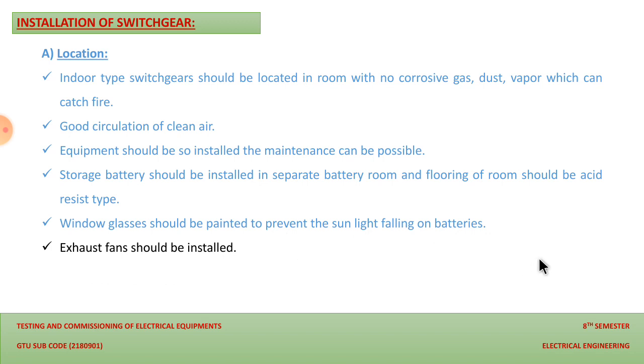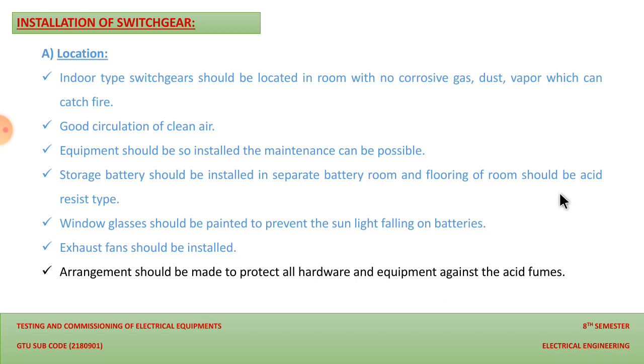So this is necessary for the proper ventilation. Then the arrangement should be made to protect all the hardware and equipment against the acid fumes. So yes, this point is again unnecessary, as we have already discussed that the floor must be acid resistant type. So after installing, we can take certain steps to protect our switchgear from some hazardous things like acid and oil. So the proper protecting hardware or equipment is required to protect our device from such things.